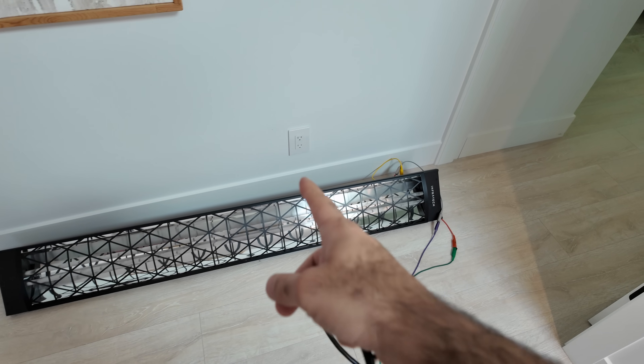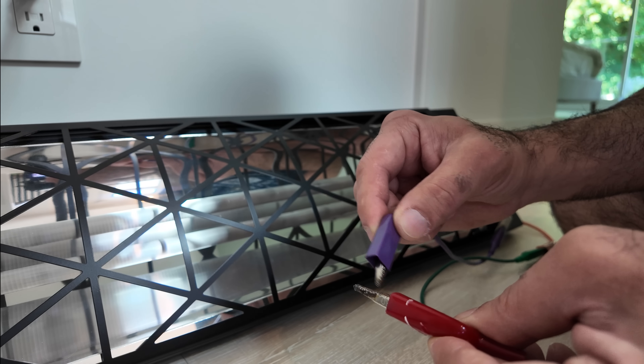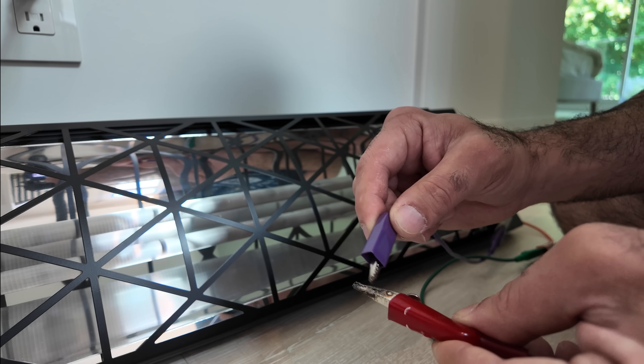For a sanity check, I brought my heater to connect it to another outlet that is on a different AFCI to see if it behaves the same. So it's not the AFCI — it's the type of my arcs for some reason that doesn't excite the AFCI breaker enough.